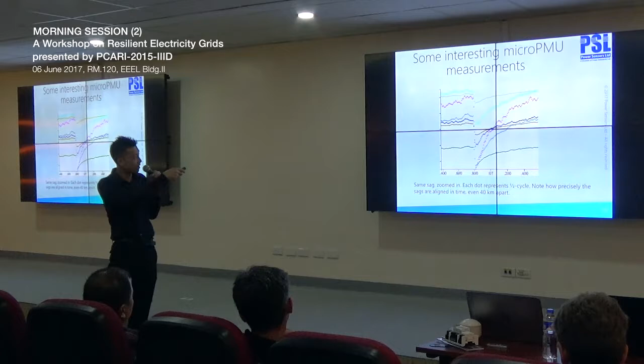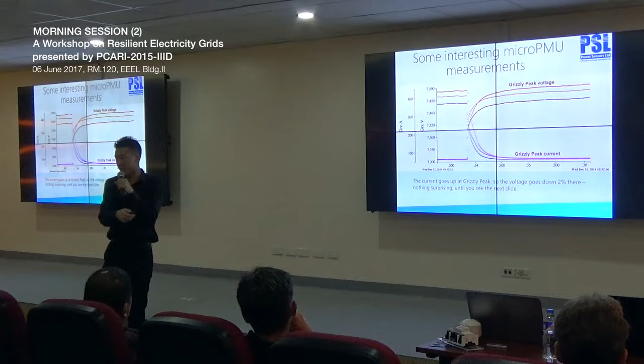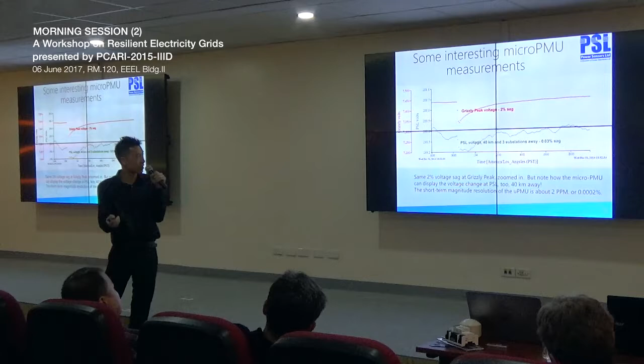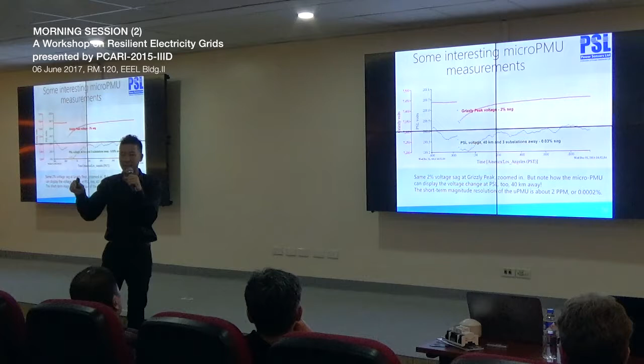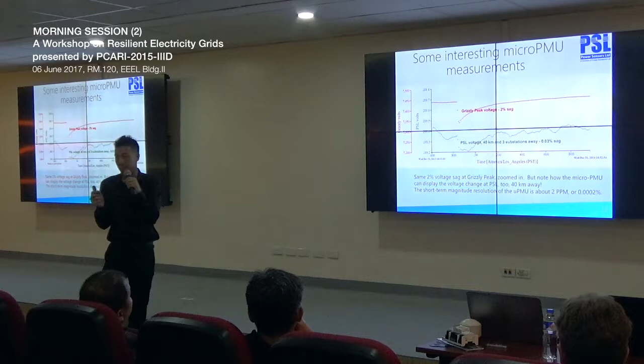Here we have a voltage dip recorded at Grizzly Peak, caused by a large load kicking in at that same location — about a 2% voltage dip, which is pretty common. But what's notable is that we could also pick up the voltage at our main office at the exact same time: instead of a 2% dip, we measured a 0.03% sag at exactly the same moment. So this load kicking in 40 kilometers away, across 3 substations, was still picked up by our micro PMU. That shows just how precise our measurements are.